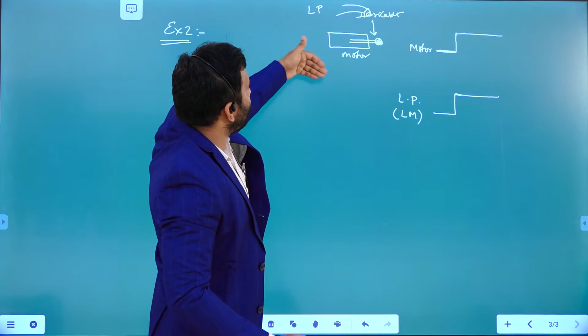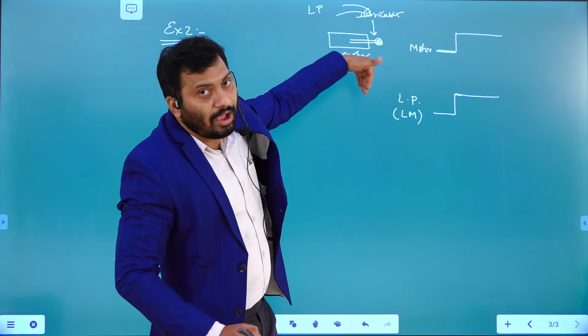Why? Because to smoothly run this mechanical device, the lubricant pump and motor are on at the same time. But even after you stop the motor, that is what you call the coasting time. During that coasting time, the lubricant pump is also going to stay on. The motor keeps running, and after some time, 10 seconds or 20 seconds, it needs to stop. During that time you also need lubricant pumped from the lubricant motor. After that the lubricant motor goes off along with the motor.